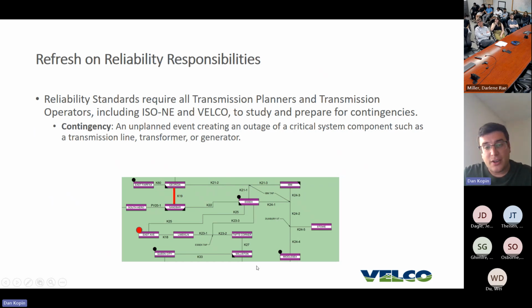In this particular diagram, you can see that this K19 line out, we planned for that, as well as this outage of a generator connected at East Avenue. In this case, we look at the system and run a power flow analysis for this exact contingency to protect against a situation in which we are exposed.